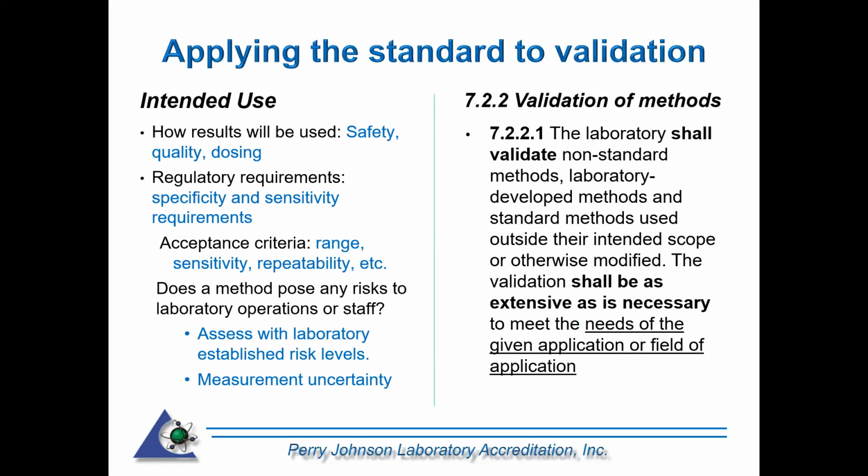The part of the standard that we are looking at in general is 7.2, which covers selection, verification, and validation of methods. And I want to talk specifically about validation of methods. There is more work, or you need to establish more performance criteria when you are looking at the validation of a method versus verifying a standard method. In validation of methods, you need to establish that the method can meet all of your acceptance criteria. So that's why I laid intended use right next to validation of methods.